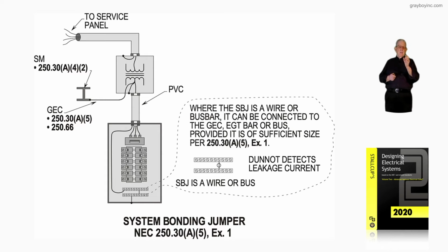Are we having a current flow beyond a setting maybe that we would have on a sensing device or whatever? So the donut that you see there detects leakage current. And then where the system bonding jumper is a wire or a bus bar, it can be connected to the grounding electrode conductor, EGT bar, or bus provided it is of sufficient size in accordance with 250.30(A)(5), exception number 1.